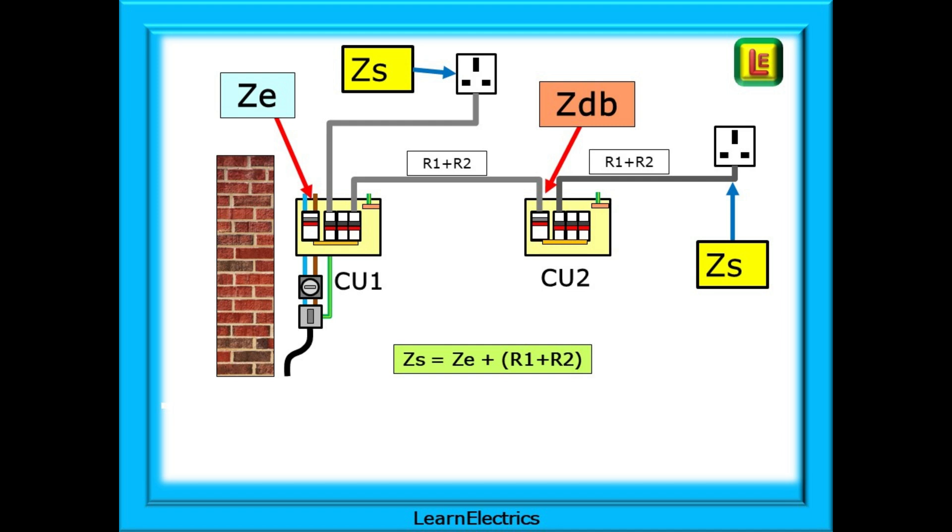We have a ZE at the incoming position and a ZS for the socket circuit. We have a distribution circuit that goes to CU2 and we call this ZDB. CU2 has final circuits with their own R1 plus R2. So ZS for these final circuits will be made up of ZDB plus the R1 plus R2 that comes after the ZDB.